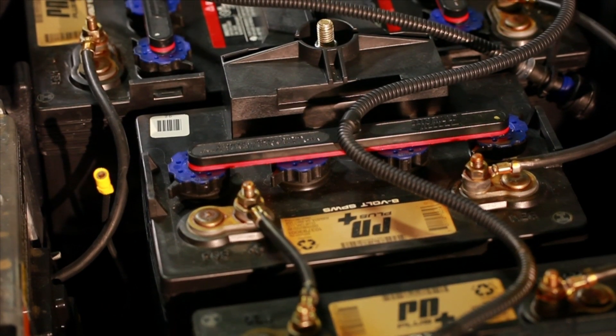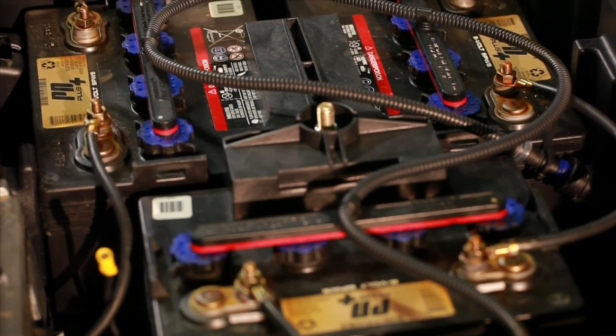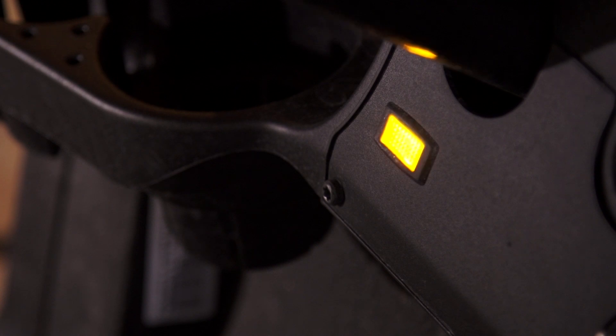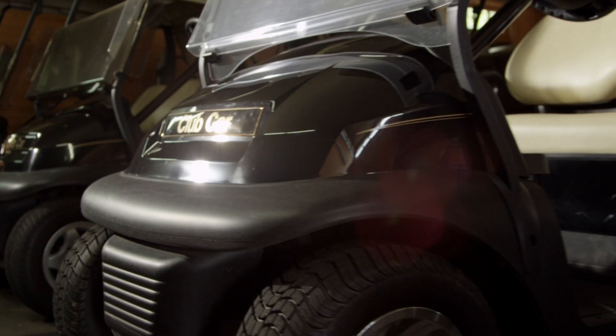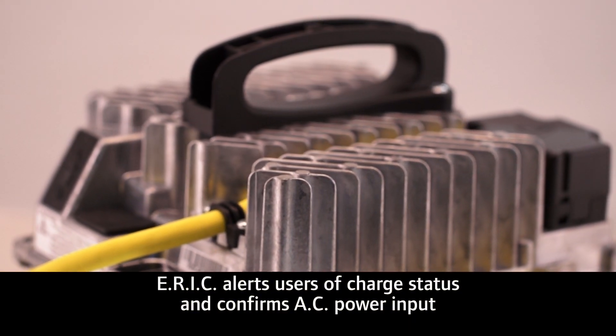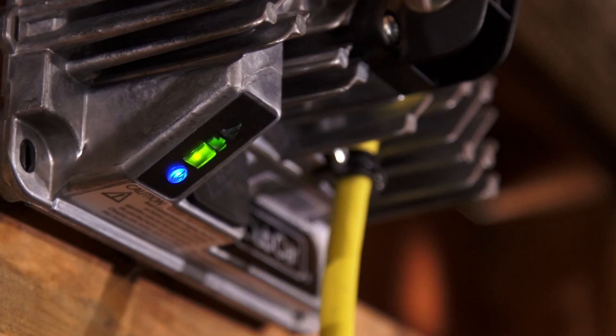ARIC is also one smart dude. It monitors the voltage in the battery pack and, when needed, sends just the right amount of electricity to fully charge the batteries. It also turns on if voltage in the battery pack is as low as 8 volts, protecting cars stored over a long period in cold climates. ARIC is so smart it can even alert you to the charge status, confirm that the charger is receiving AC power, and identify charger faults — all with a system of colored lights and audible alerts.